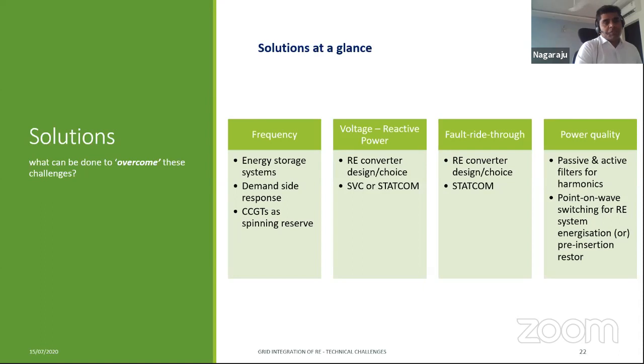Then for voltage dips, one of the issues that I have not explained here in terms of challenges is energization. When you're energizing the wind farm or solar farm, they can create voltage dips on the grid. And there are strict regulations by grid operators on what level they can go in terms of voltage dip. Because these wind farms have a lot of cables and transformers, they do create a lot of voltage dip because they are energy sources.